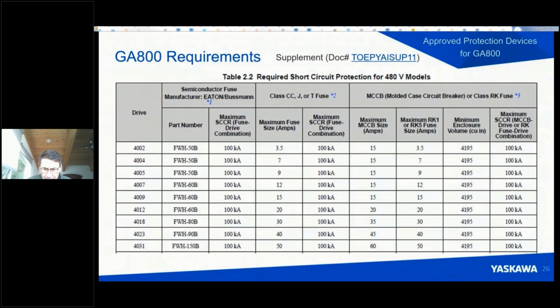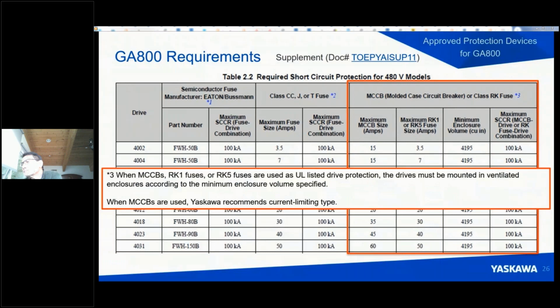Okay? And here's an example of the GA800. You can see that we show the use of semiconductor fuses. We show the use of what I would call conventional fuses, being class CC, J, or T, and also the limitations associated with using a molded case circuit breaker or an RK fuse, which you can kind of think of as the same. In all cases, the maximum SCCR rating of the GA800 is 100,000 amps, no problem, but there are conditions of use. In the case of a molded case circuit breaker, as I mentioned before, that can no longer be your means of protection for a drive that's not enclosed, and we make note of that in the manual. So please be aware of that.